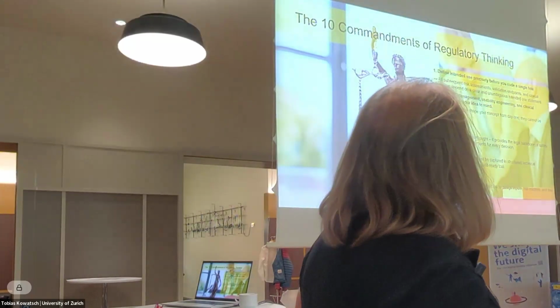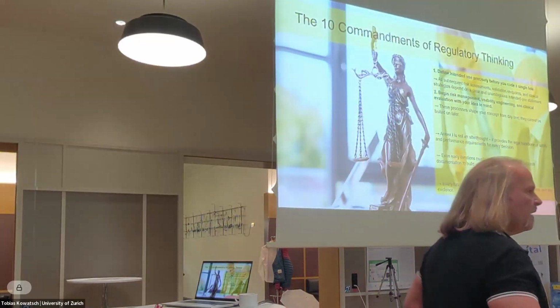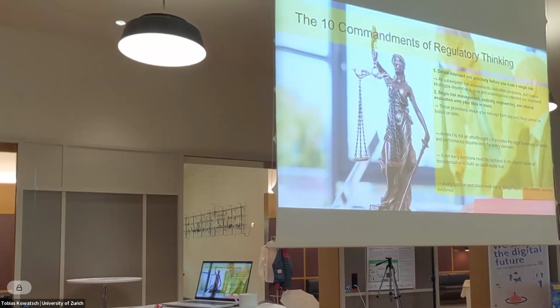Second, begin risk management, usability engineering, and clinical evaluation with your idea in mind. Once you have your prototype in your hand, it's too late. Because risk management really starts in your mind. If you have an idea, you can think about risks. And risk mitigation is to design a medical device to avoid any risk. And so this starts with your idea. The same is true of usability. You can think about usability, how to handle the device, with the idea in mind. Avoid sharp edges, think about a clean picture on the screen. You don't want to discover with the prototype, oh, it can't read anything. So it starts at the beginning.